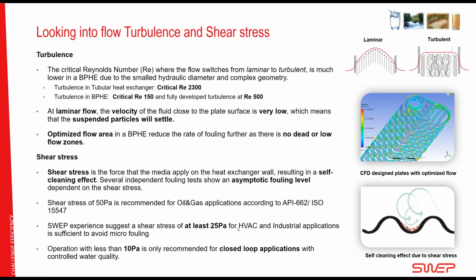It could be that HVAC and oil and gas is more demanding than most of the applications that we see. We also have applications with less than 25 pascals and also lower than 10 pascals of shear stress. But when you're at 10 or below, we would recommend that for closed loop applications with controlled water quality. Because if you have a fairly good water, there will be no fouling in some way. If you have reasonably good water and it's a closed loop and there is no infiltration of clay and dirt and stuff like that, you don't need to work against the fouling because there is nothing to foul. But otherwise, to be better safe than sorry, 25 pascals is our gentle suggestion, and this is also where we had this disclaimer in the beginning.